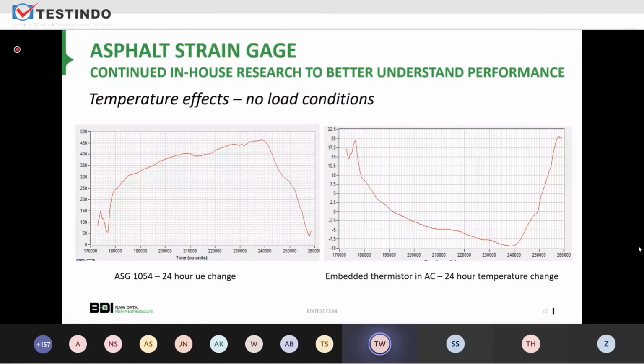So this is very helpful—it provides feedback to our users. When they measure this information, we can talk intelligently and have a better understanding of the data they're seeing from temperature effects, and provide recommendations on how to correct for temperature in unloaded conditions. It also helps them understand that if you're going to trigger your strain gauge, you need software algorithms that measure that drift and trigger based on a change of strain on a rolling average, not just a change in strain, because temperature can trigger your data acquisition system when you don't want it to.